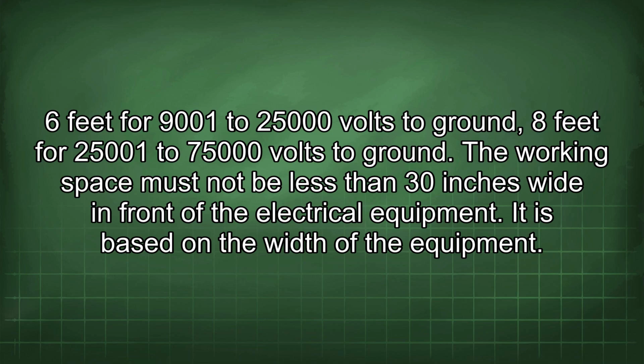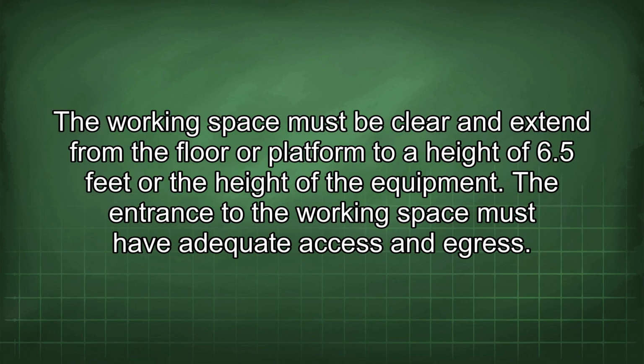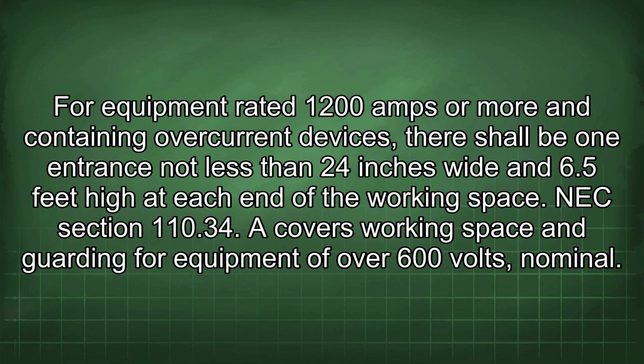The working space must not be less than 30 inches wide in front of the electrical equipment. It is based on the width of the equipment. The working space must be clear and extend from the floor or platform to a height of 6.5 feet or the height of the equipment. The entrance to the working space must have adequate access and egress. For equipment rated 1200 amps or more and containing overcurrent devices, there shall be one entrance not less than 24 inches wide and 6.5 feet high at each end of the working space.